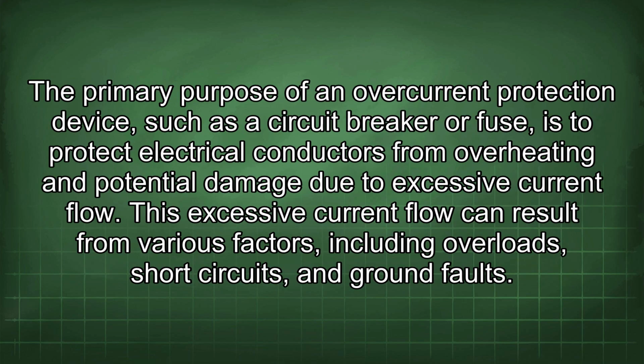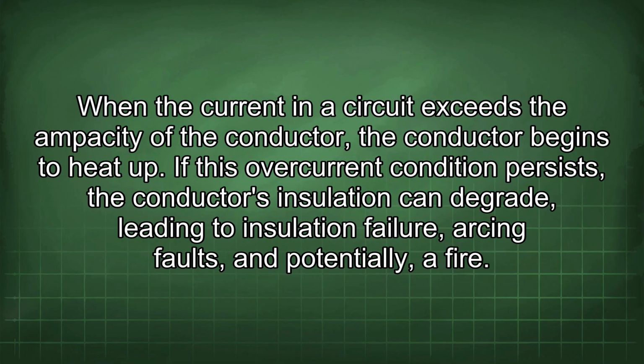The primary purpose of an overcurrent protection device, such as a circuit breaker or fuse, is to protect electrical conductors from overheating and potential damage due to excessive current flow. This excessive current flow can result from various factors, including overloads, short circuits, and ground faults. When the current in a circuit exceeds the ampacity of the conductor, the conductor begins to heat up. If this overcurrent condition persists, the conductor's insulation can degrade, leading to insulation failure, arcing faults, and potentially a fire.